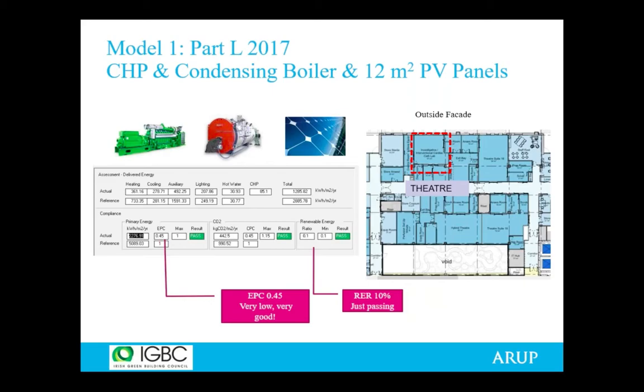The test showed that for this operating theatre, CHP plus a boiler plus PV panels complied with the new NZEB minimum regulation, with a very low EPC value, which is very good, but with only 10% on renewables. So it was just passing. For those not familiar, if the EPC is below 0.9, your renewable target can be only 10%.